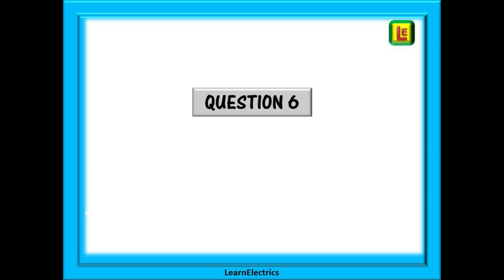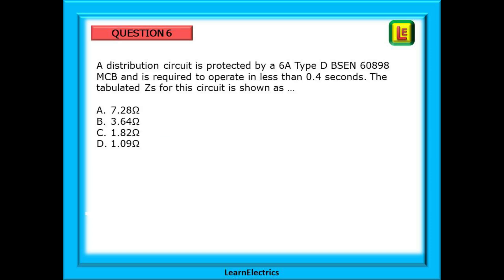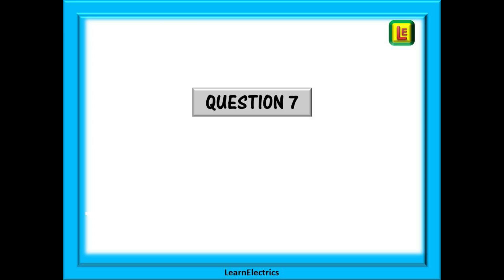Now, question 6. We are asked: A distribution circuit is protected by a 6-amp type D BS EN 60898-MCB and is required to operate in less than 0.4 seconds. The tabulated ZS for this circuit is shown as... Pause the video and answer the question. You should choose answer C, 1.82 ohms.